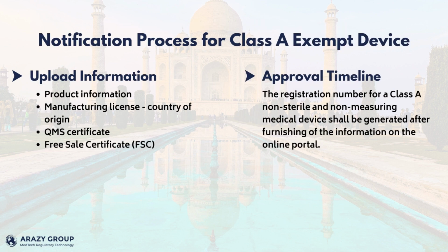To notify Class A exempt devices, the manufacturer must upload information or documents such as product information that includes the name and address of the importer and manufacturing site, generic and brand name, model number, intended use, material, dimension, and shelf life, a manufacturing license issued by a competent authority in the country of origin, a QMS certificate, and a free sale certificate issued by the National Regulatory Authority.